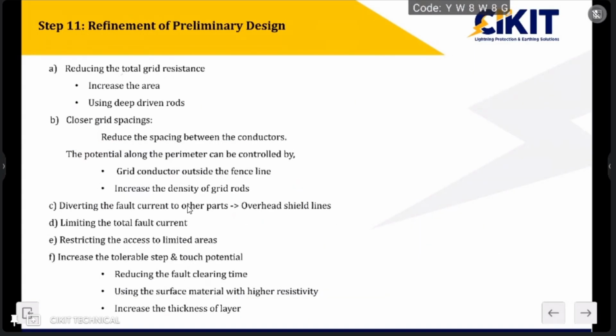So if we are performing this design, first we have calculated the tolerable value, then in the last step we have calculated the actual values. We need to ensure that the actual step and touch voltages are within the tolerable value. If the actual step and touch voltages are within the tolerable value, the design will be considered as safe. In case the actual values are greater than the tolerable value, then what do we have to do? We have to redesign this earth mat and ensure that the step and touch voltages are within the tolerable limit.